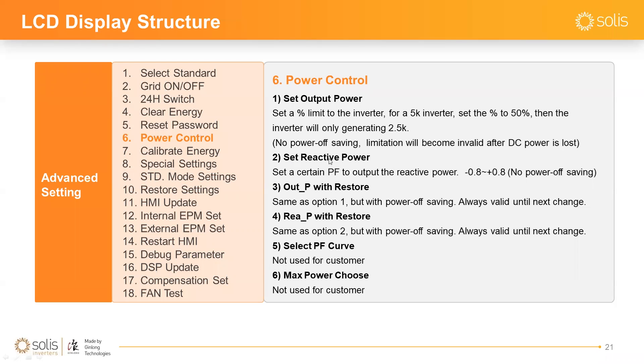You can also set reactive power (power factor) in Power Control — from 0.8 leading to 0.8 lagging. Similarly, this setting is not persistent; use 'Reactive Power with Restore' to save it. The next two settings in Power Control are not intended for customers.